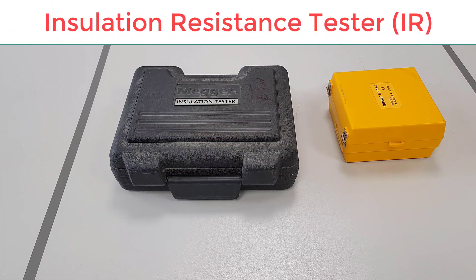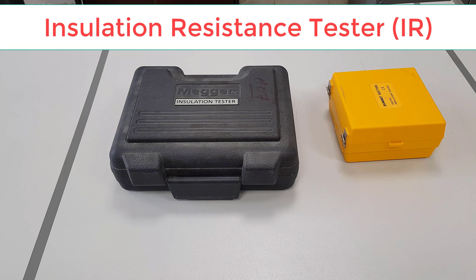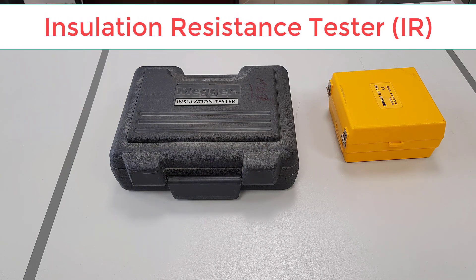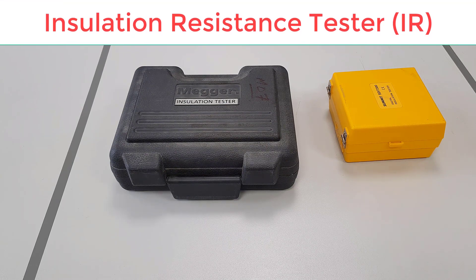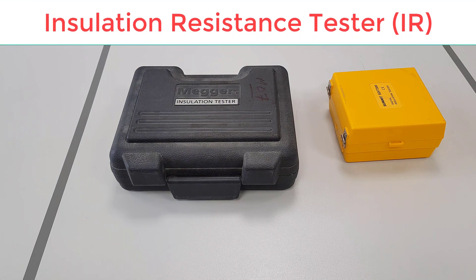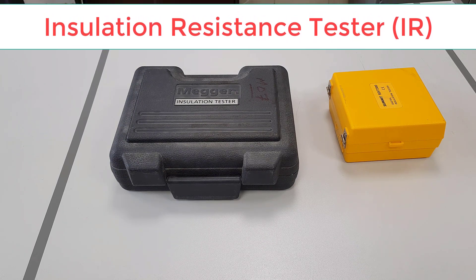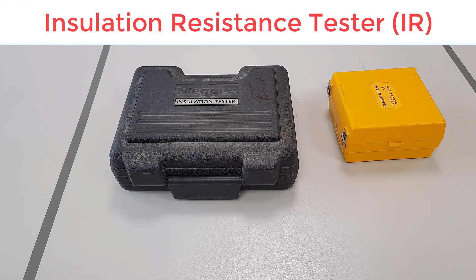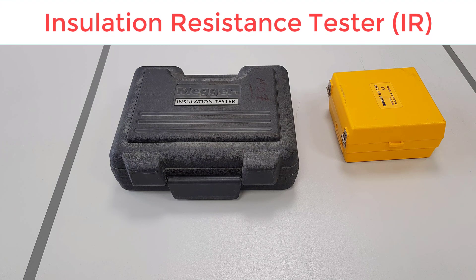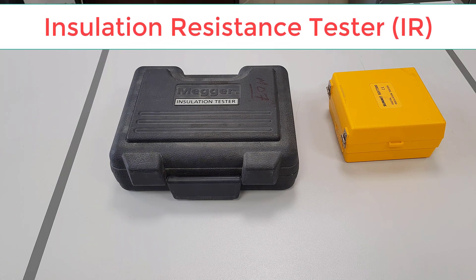An insulation resistance tester, also called a megohmmeter, is used to measure the ohmic value of an insulator under a direct voltage of great stability. To measure a high resistance, techniques for measuring low current are used. A constant DC voltage source is applied to the resistance to be measured, and the resulting current is read on a highly sensitive ammeter circuit that can display the resistance value.